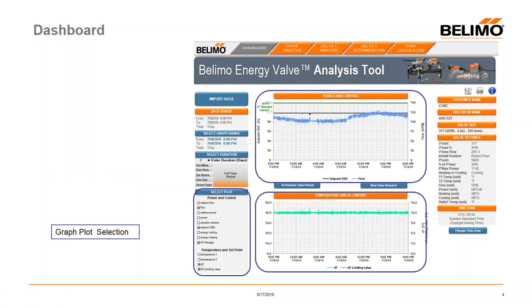The next section allows you to select which plots you'd like to see on your graphical analysis. On the top is power and control, and on the bottom is temperature and delta T limiting. By clicking on different values — such as relative flow, absolute flow, power, DDC set point, cooling, energy, or delta T managing — you select the graph that will show over the selected time period exactly what the valve is doing.